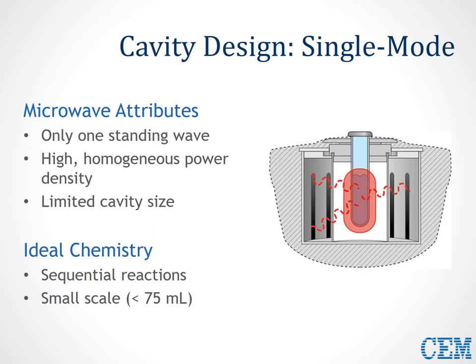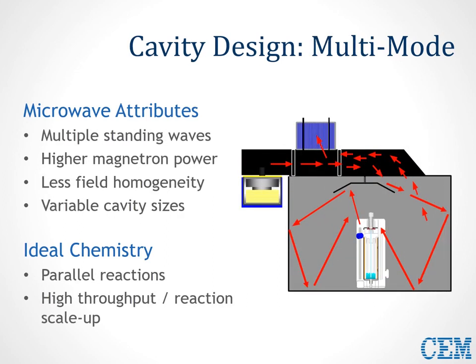There are a couple of different types of scientific microwaves available. The single-mode microwave is designed to allow one standing microwave inside the cavity, creating a high homogenous power density. It limits your sample size based on cavity size and is ideal for sequential reactions at smaller scales — about less than 75 milliliters. Multi-mode microwaves are a lot like your standard home microwave. These have variable cavity sizes and allow multiple standing waves inside the cavity with higher magnetron powers, but less field homogeneity — meaning potential for hot and cold spots, which you address through stirring and rotating the sample. Multi-mode microwaves are ideal for parallel reactions and scale-up reactions.